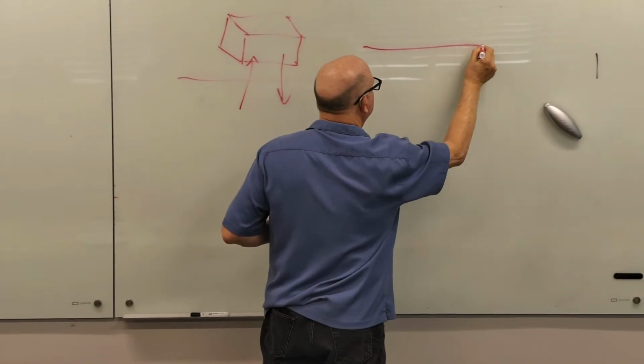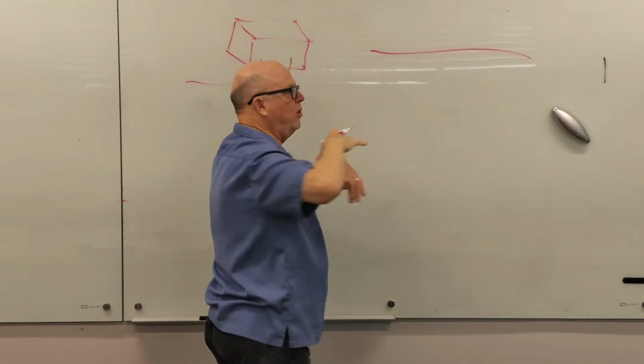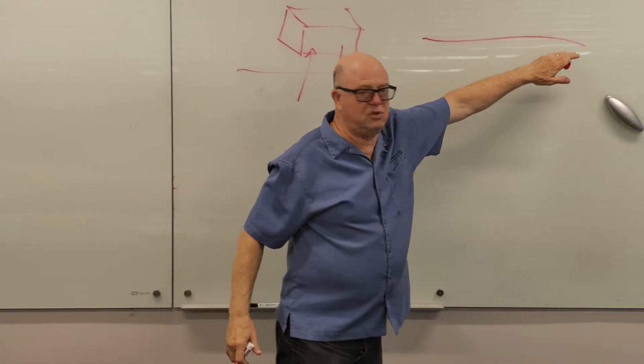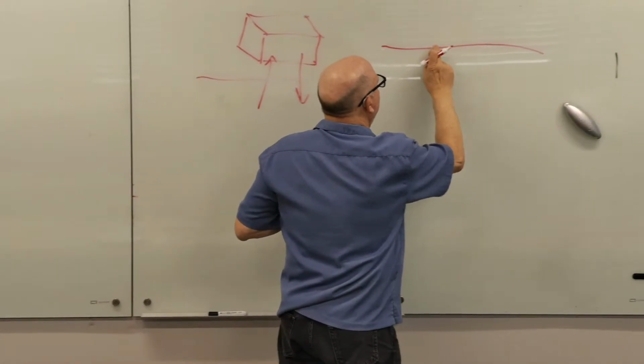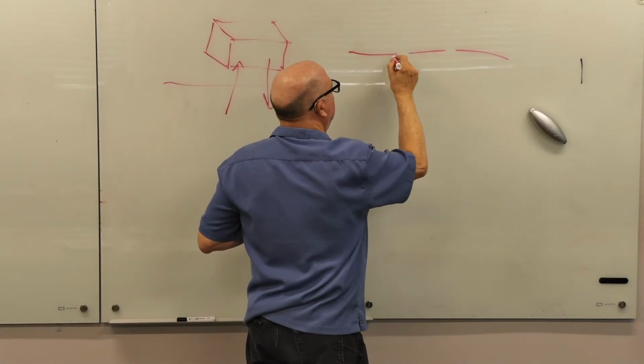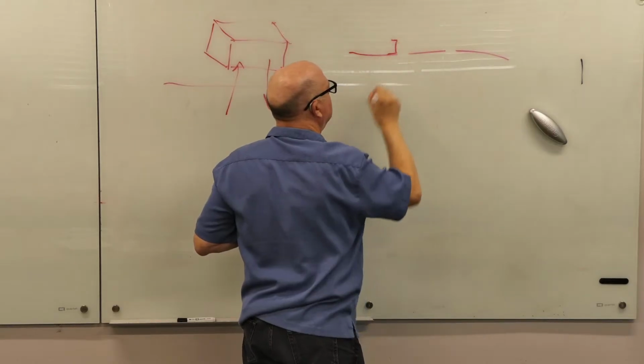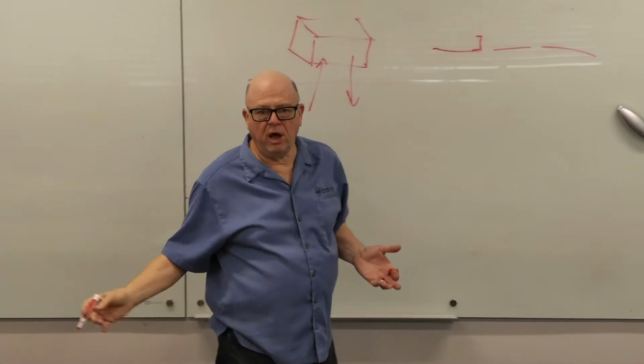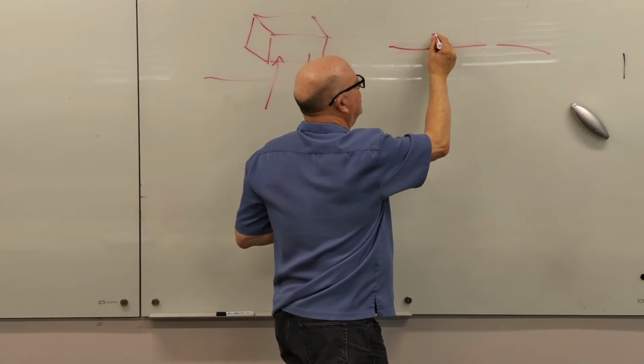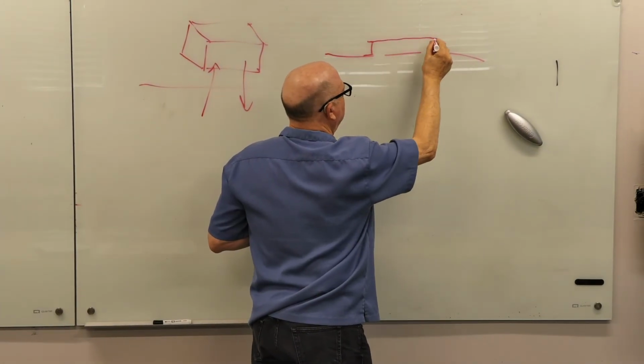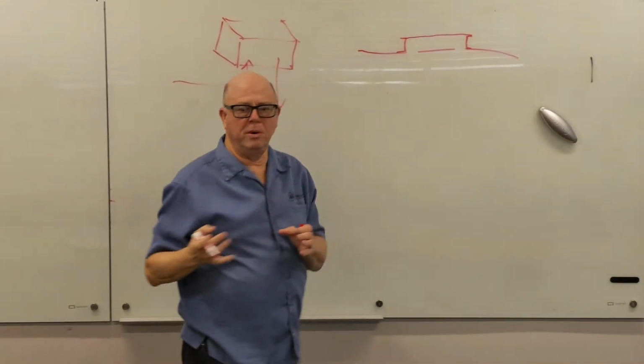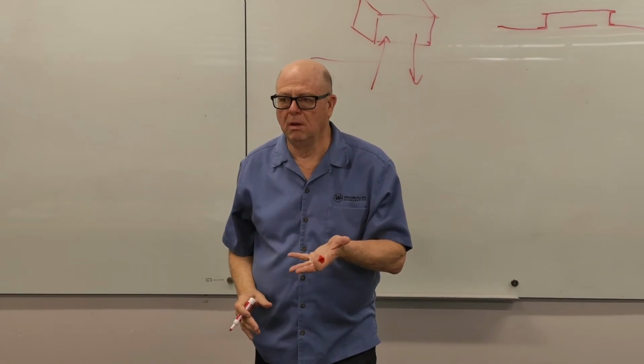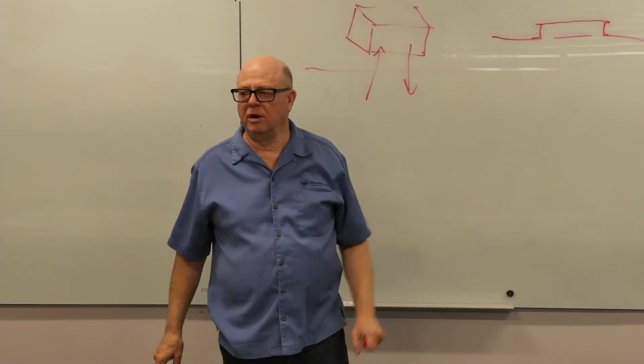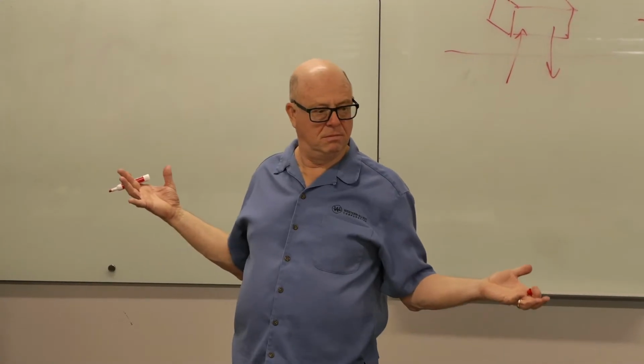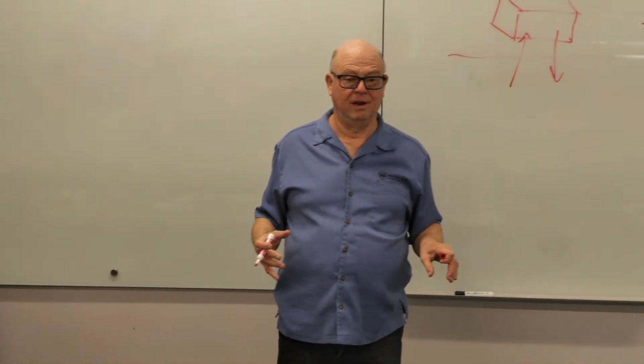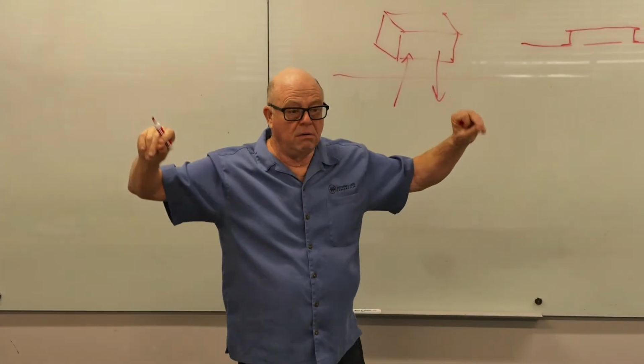See, here's your roof surface, and before you put the final roofing on, this is just the structural roof. You'd have the hole that the return and supply duct were coming through, and you'd have this curb. If it was an 8-inch curb, that'd be 8 inches high. And then the rooftop unit would go across, and you'd have a curb that went all the way around the perimeter. That's pretty simple. So what goes on top of the structure? Insulation. And then some kind of a membrane that isn't going to leak water.